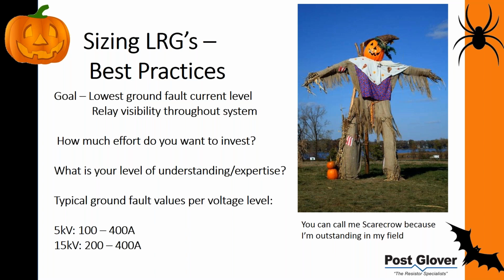But one of the things I get all the time is, from a gen dealer, and no offense to gen dealers, but they're not the system engineer, they're not the design engineer, and they need to specify this current. Well, you should just throw all that out the window, in my opinion, and say, look, I don't have intimate knowledge of a relay system and what its capabilities are, how far the faults are going to be, where all my motors are going to be, et cetera. So I would just use common practice, which is, typically for 5 kV, we're talking about 100 to 400 amp resistors. When I say 100 to 400 amp, I just mean let-through current, right? Ground fault current. For 15 kV, 200 to 400 amps, those are most common for most applications.